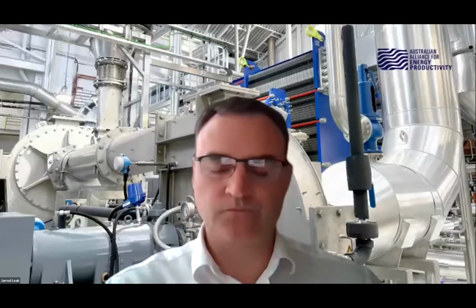Excellent, thank you. Absolutely - what we could get away with 15, 20 years ago in terms of just measuring amps doesn't fit these days because the cost of metering is so low. If you want anything accurate these days, you've got to put real energy meters in to get that proper data. As Michael said, it's all about power factor, load, and voltage, and the technology these days allows that very cost effectively.